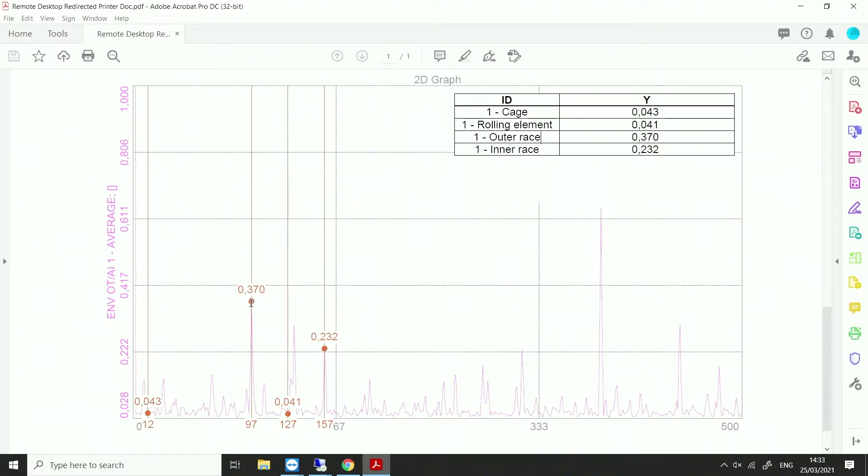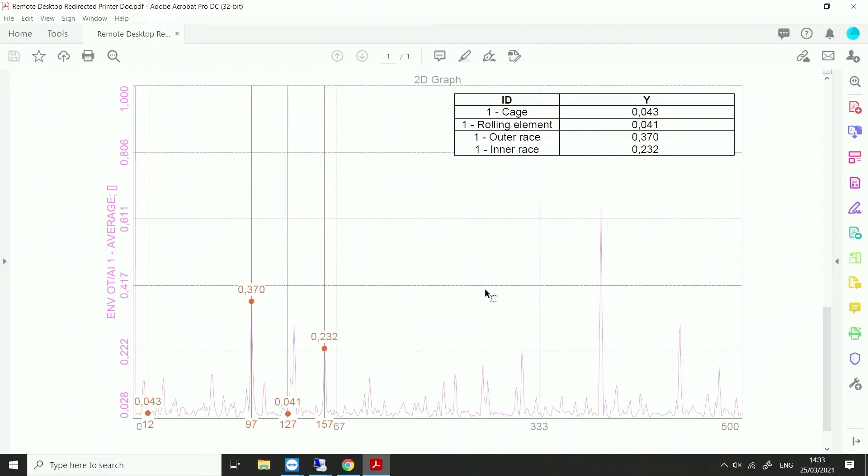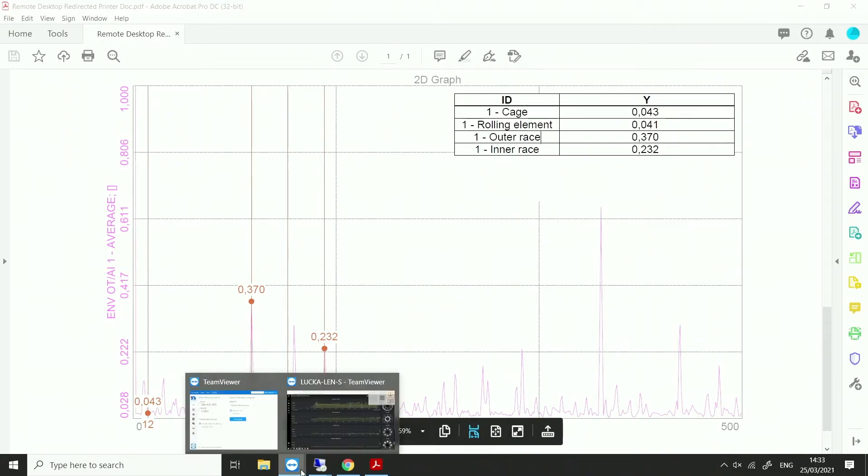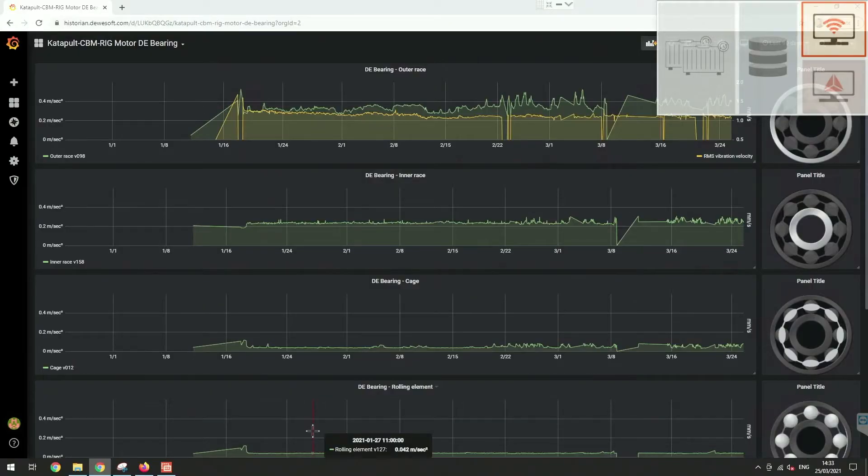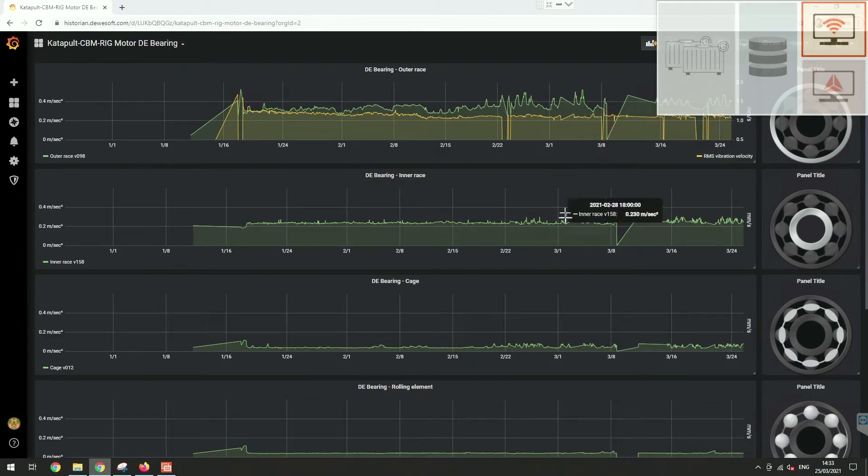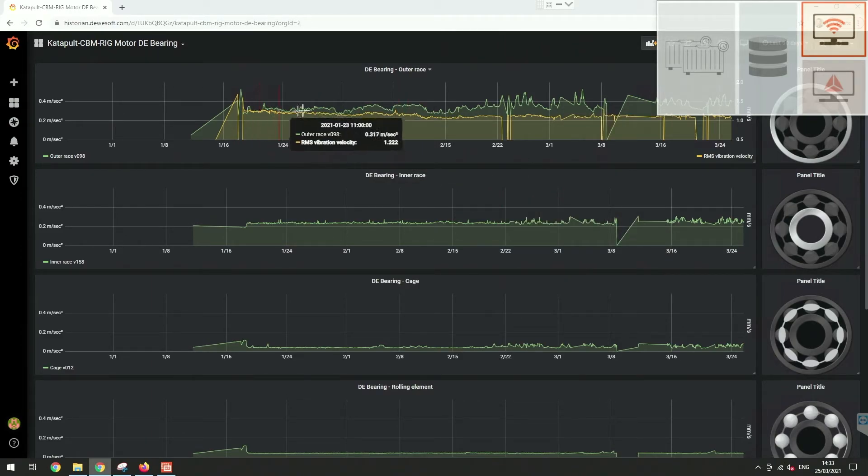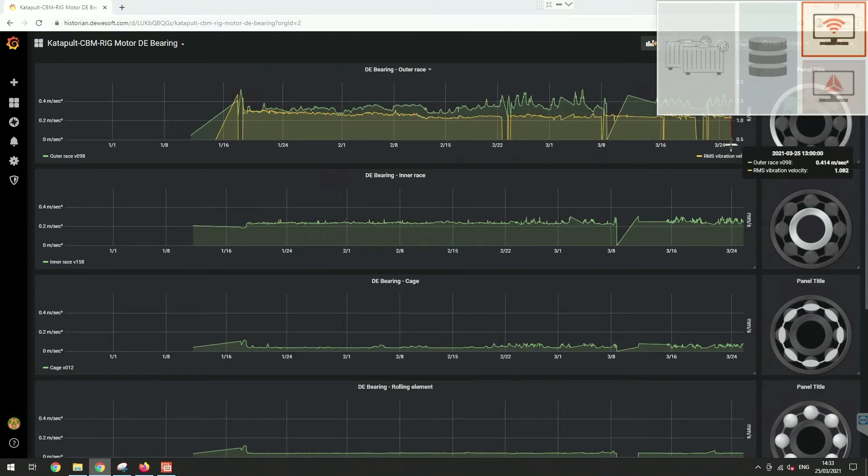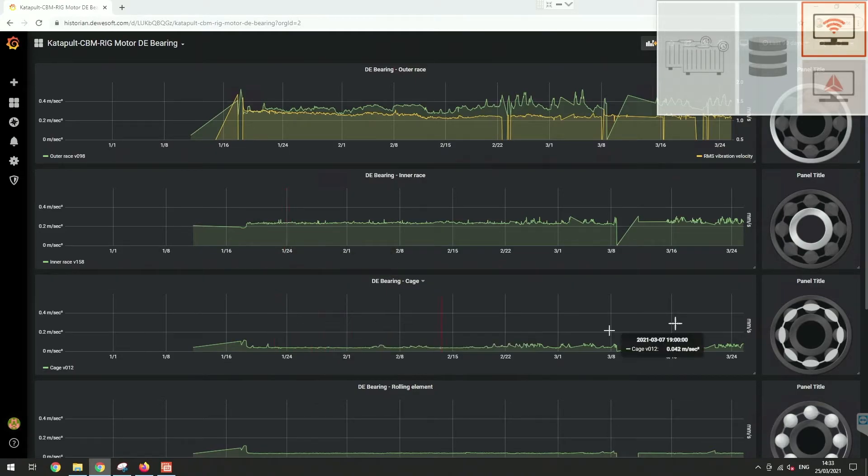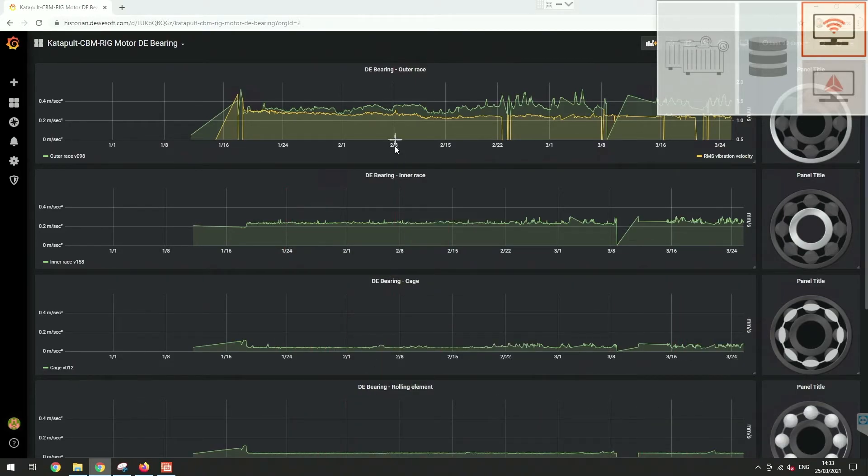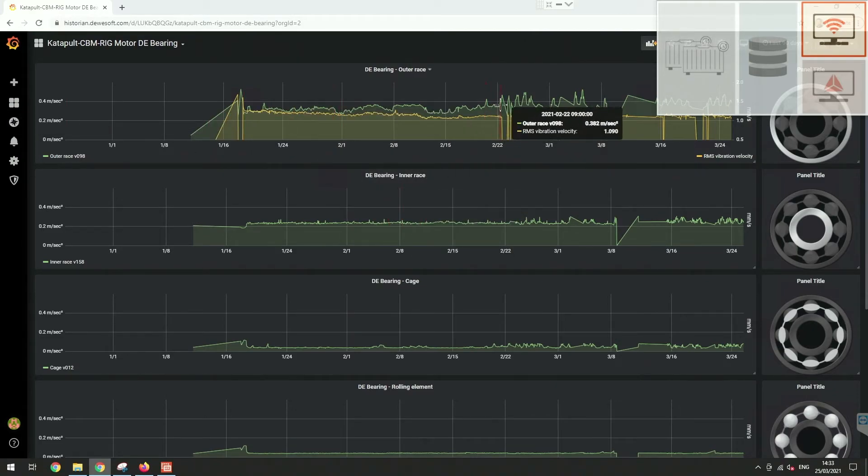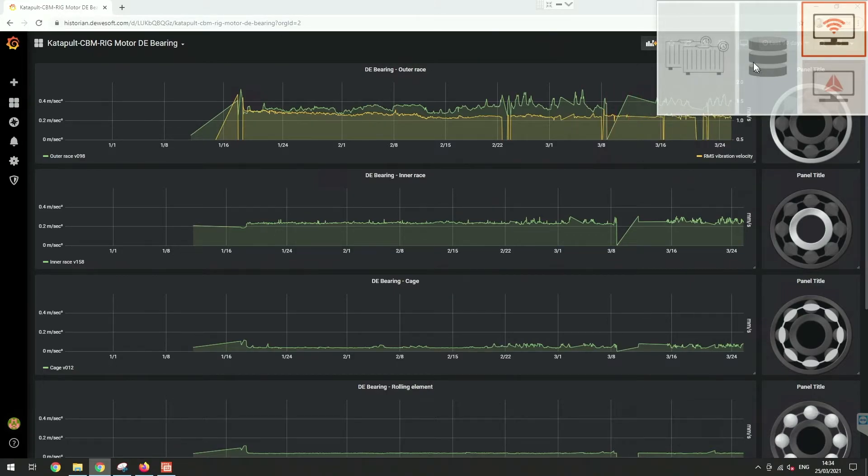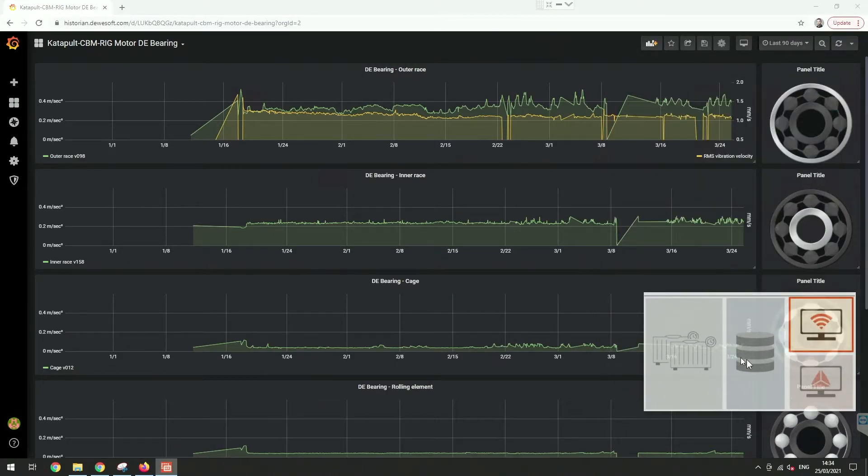This is the web client, and we are plotting each of the amplitudes. As you can see, this is the outer race amplitude, this is the inner race amplitude, this is the cage, and this is the rolling element. The scales are all the same, so we can see that the outer race is the highest, but also we can see that it is actually slowly growing.